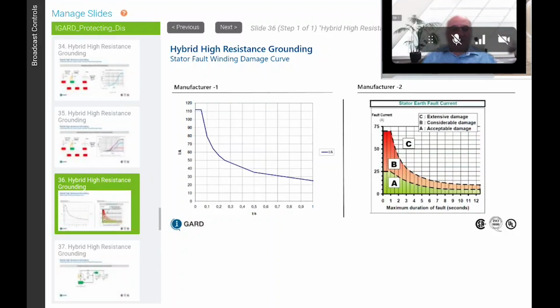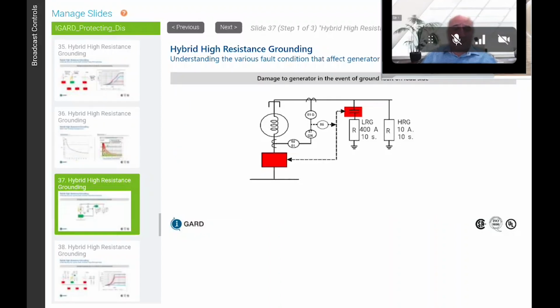Why this is important is because we have two manufacturers of alternators here, and they state the stator fault winding damage curve: this one can handle 110 amps for less than 500 milliseconds. This one over here shows acceptable damage, considerable damage, extensive damage. Extensive damage starts at 75 amps. So IEEE got together and a lot of the brilliant minds came together with a hybrid high resistance grounding system.